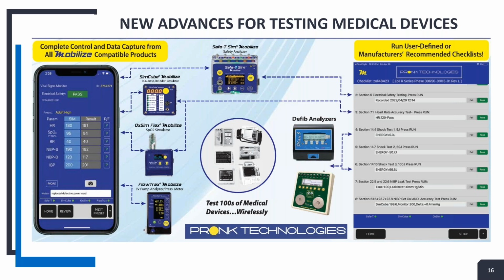There's an SPO2 test we have to do. It will also communicate to the simulator and say, run this rate. It's going to run a saturation of 70%. It's going to tell the simulator, set it to 70. The technician is going to verify the result here. So whatever automation is required, whatever testing is required, the app tells the user, run that test. The pass-fail tolerance is in there. For simulation, of course, you're going to look at the device, capture the result, and keep going.